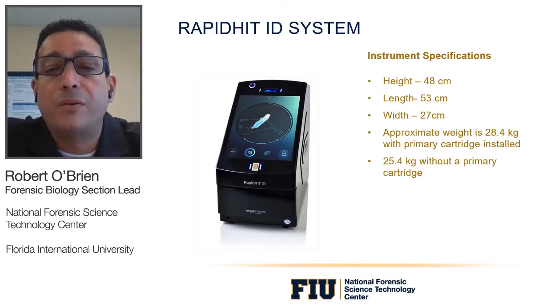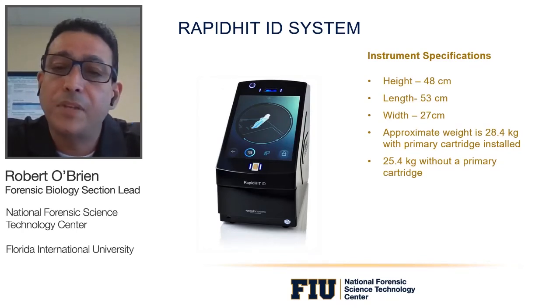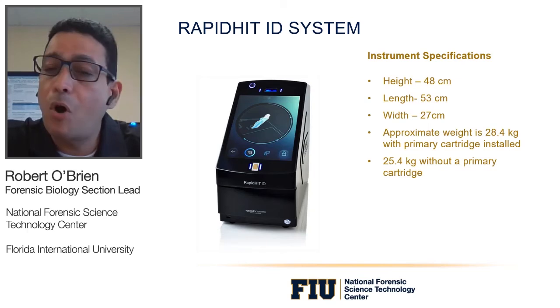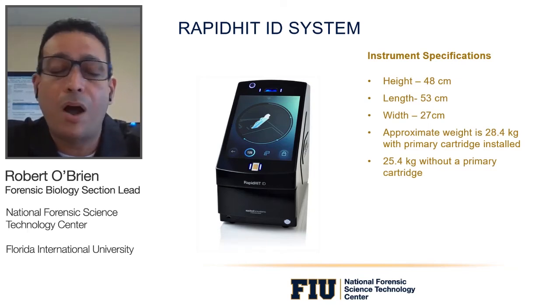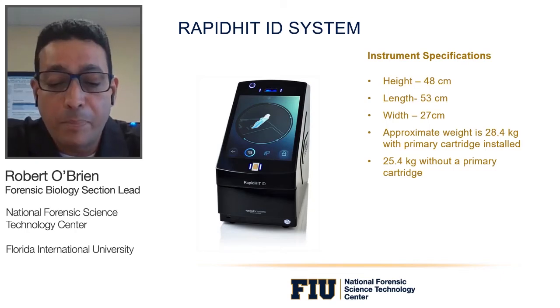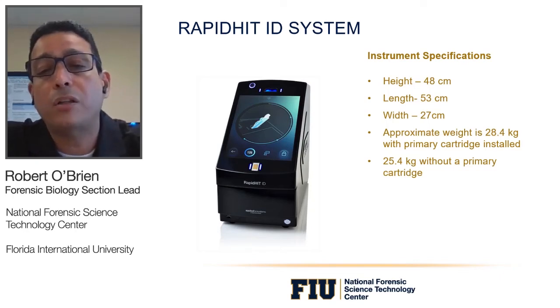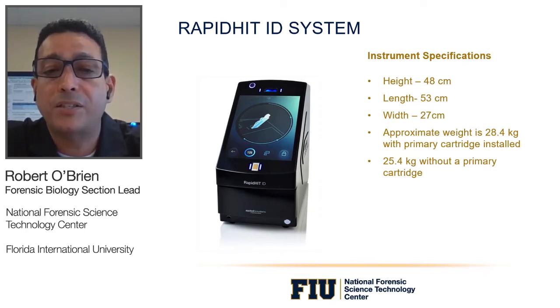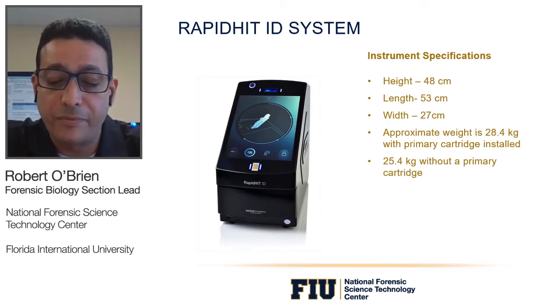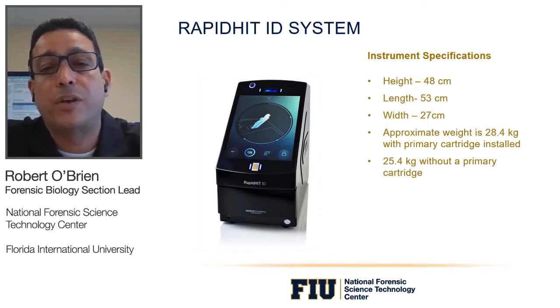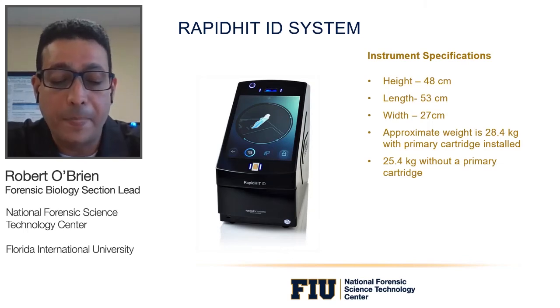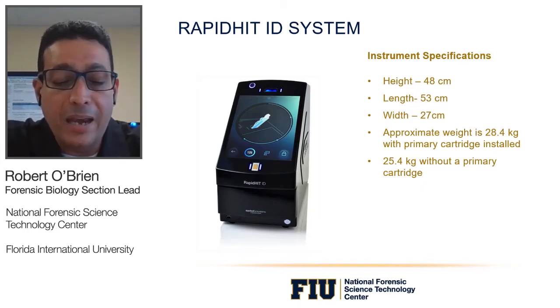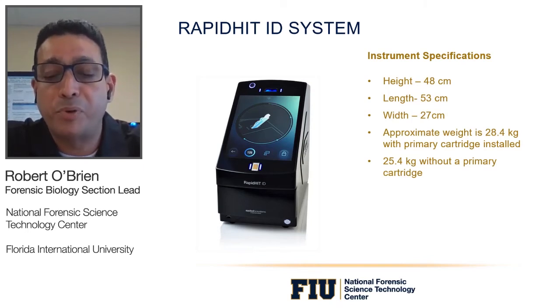Now we're going to look at the RapidHit ID system. The height is about 48 cm, the length is 53 cm, and the width is 27 cm — very small and easily placed in nearly any room, whether a laboratory or booking station. The approximate weight is 28.4 kg with the primary cartridge installed, and 25.4 kg without. The only additional space requirement may be for a laptop, but data can be sent to a centralized location, so many instruments could be placed alongside each other — expanding capability without requiring much space.